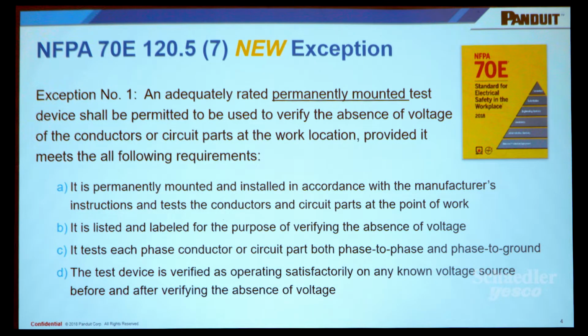So in section 120.5, step 7, there's an exception to the live, dead, live test. That section talks about taking a portable tester and following the live, dead, live procedures. Now, if it's permanently mounted and installed in accordance with the manufacturer's recommendations, and if it's listed for the purpose of verifying absence of voltage, which is the UL certification, and if it tests each phase to phase and phase to ground, then it is allowed to be a valid substitution for the live, dead, live test that's normally done manually. So that was written in 2018.